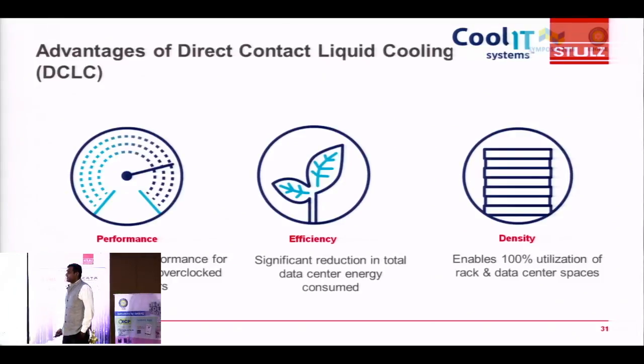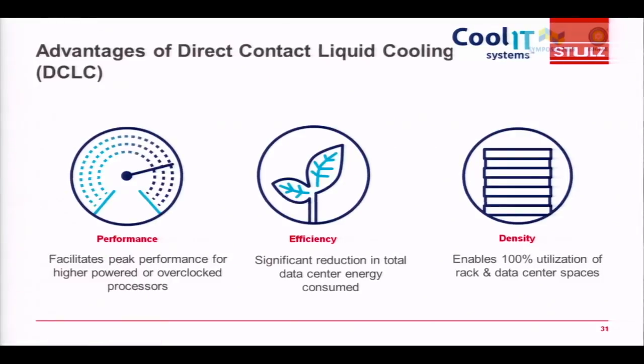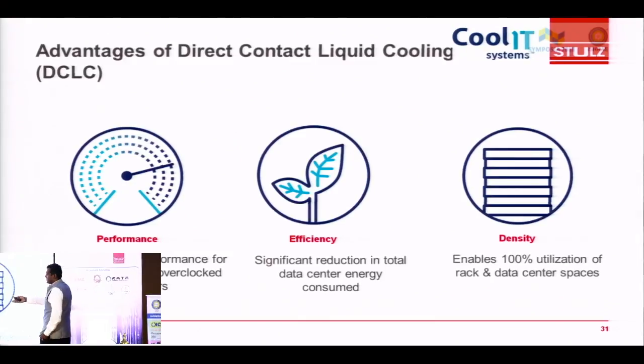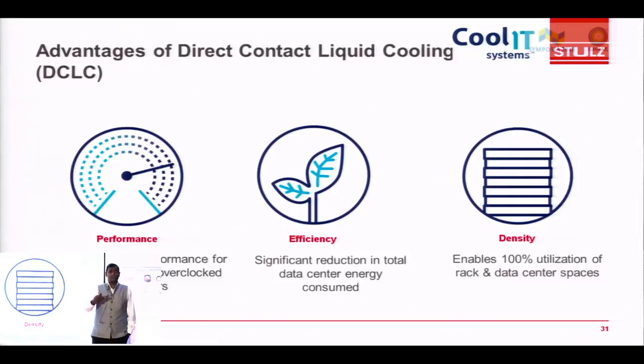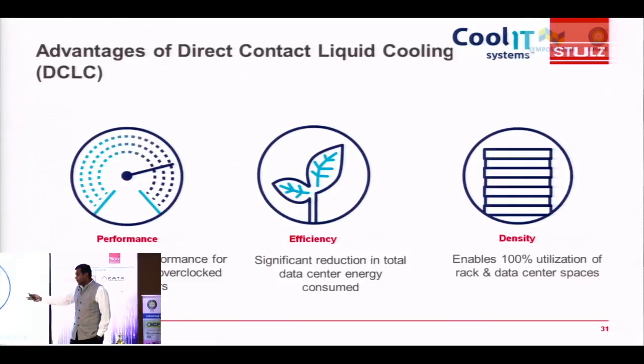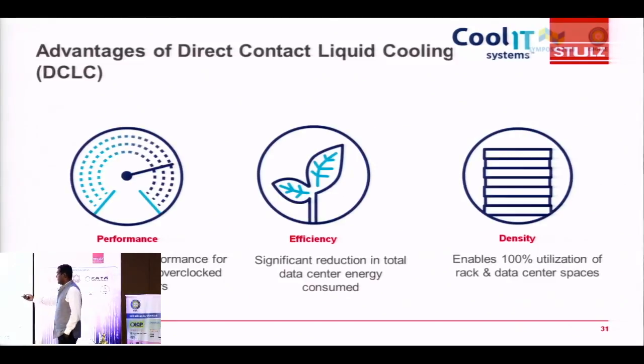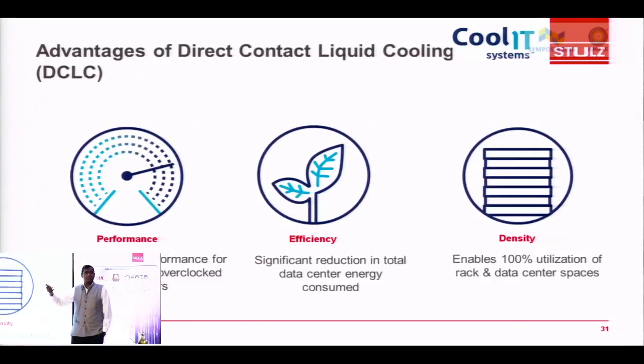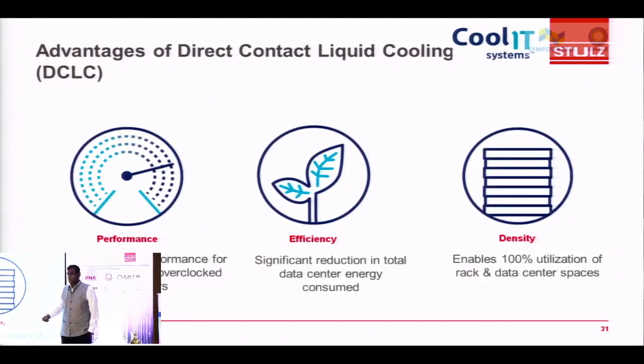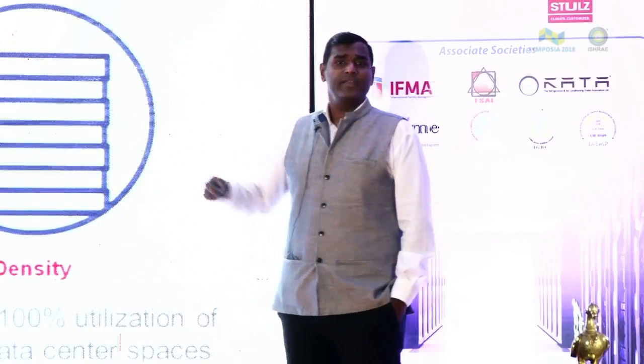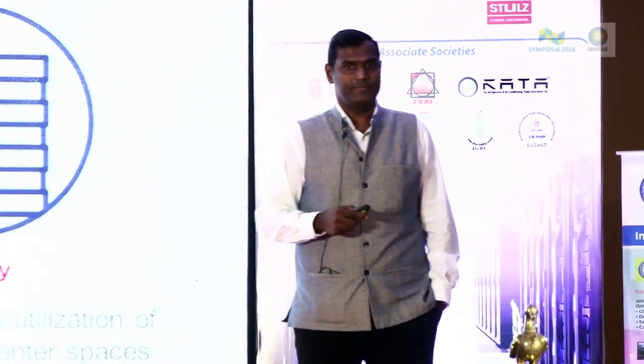Some of the advantages, very clearly, performance. You can use the equipment to the core. You could drive it up to the peak performance. The other part is efficiency. Obviously, I showed you a typical calculation. It's a no-brainer that it's highly efficient when you compare it to traditional air cooling today. From density, again, the same, the footprint. We heard about servers in pizza box style maybe 10 years ago. I mean, you can really stack up everything into this floor space and remove the heat.